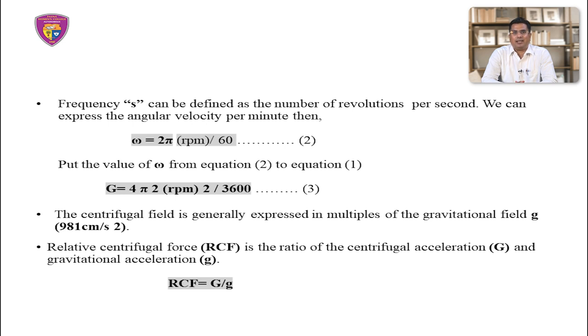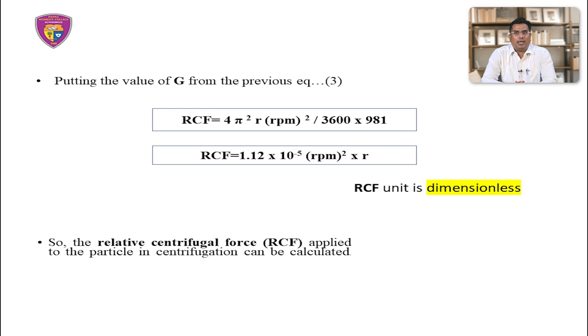Putting the value of Equation 2 into Equation 1, we get G = 4π² × RPM² / 3600 (Equation 3). The centrifugal field is generally expressed in multiples of the gravitational field g, where g = 981 cm/s². Relative centrifugal force RCF is the ratio of centrifugal acceleration G and gravitational acceleration g, so RCF = G/g. Substituting Equation 3: RCF = 4π² × r × RPM² / (3600 × 981).